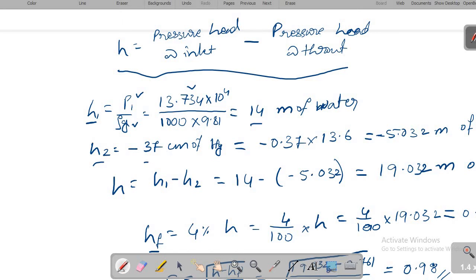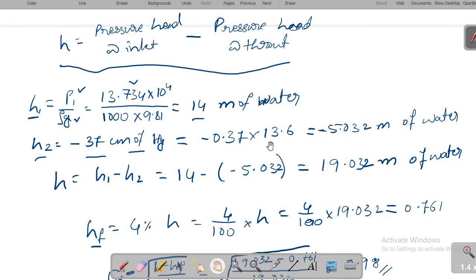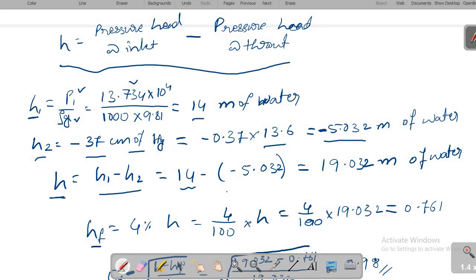H2 is 37 cm of mercury vacuum pressure, which must be converted to meter of water. Multiplying by the specific gravity of mercury (13.6), we get 5.032 meter of water, which is negative due to vacuum. So the differential head H = H1 − H2 = 14 − (−5.032) = 19.032 meter of water.